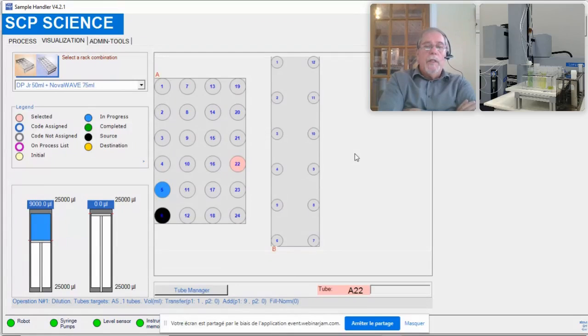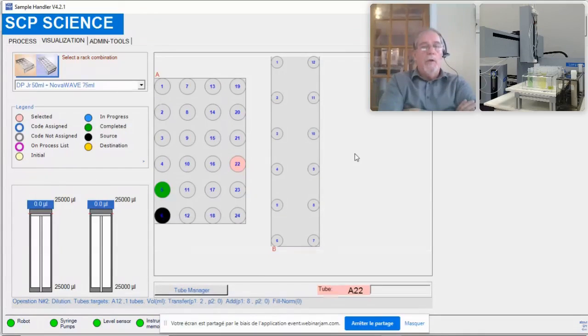So the dispensing tip has gone in. If you look closely at the screen, you can see that we have the bubble stirrer bubbling the sample. Then it's going to pick up the dilution. Then it picks up the aliquot of the sample. This way we ensure that the inside of the tube is rinsed well between samples to prevent contamination by carryover. The speed of dispensing is at 3 milliliters per second, so we have a very good mix. So typically when you're doing a dilution, the speed of dispensing ensures good mixing, so it's not necessary to stir the sample after it's been aliquoted.